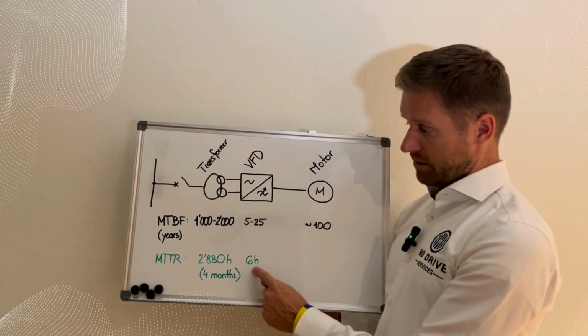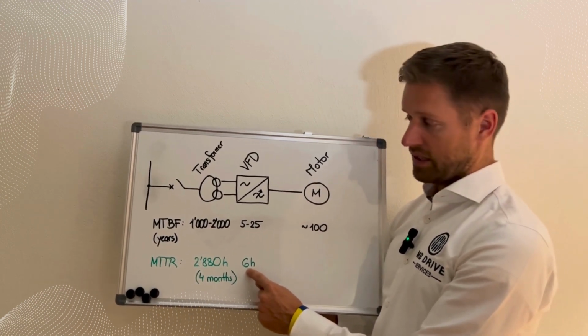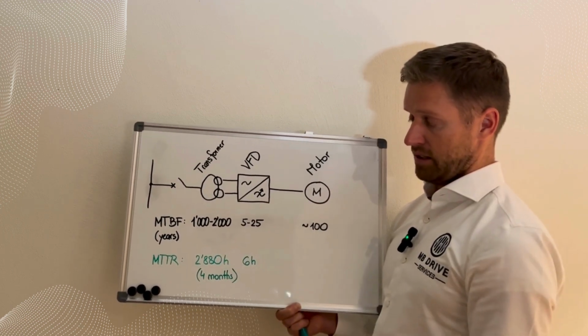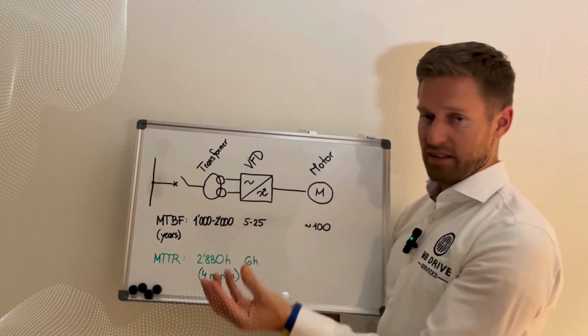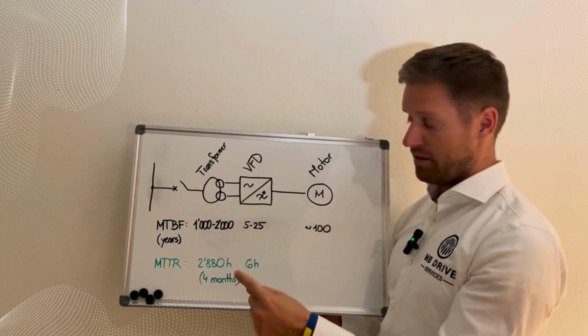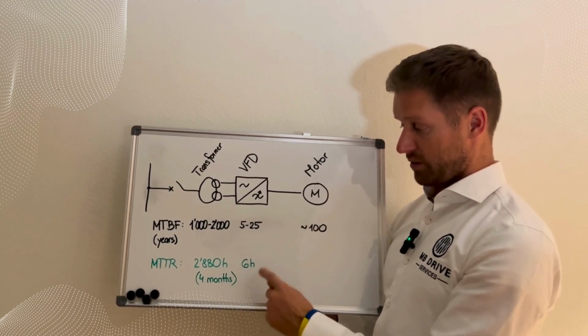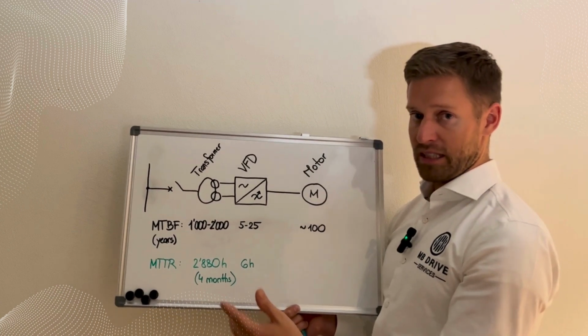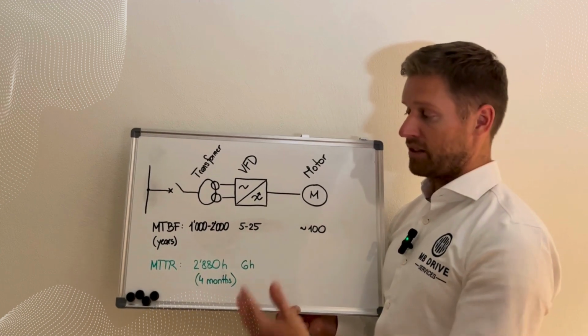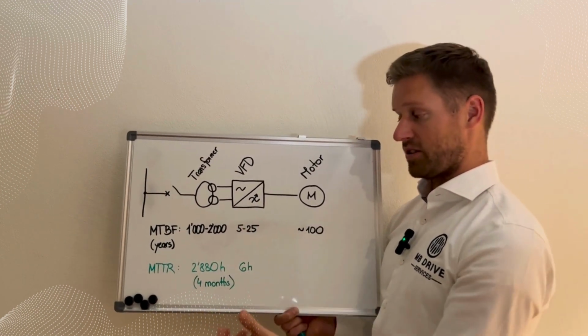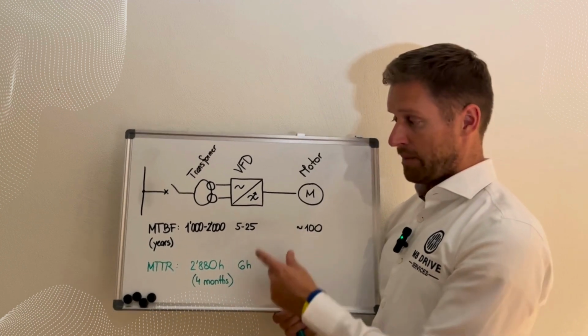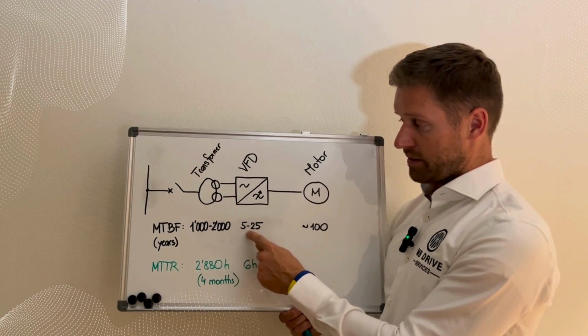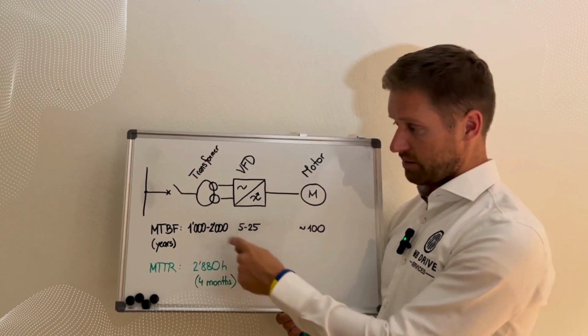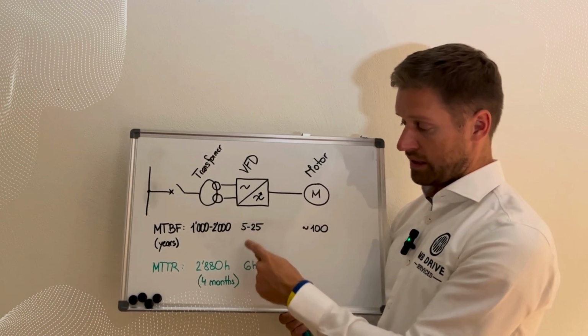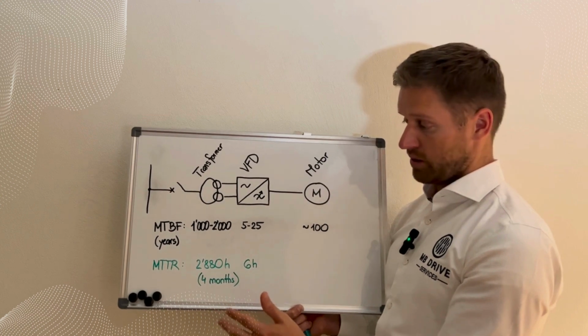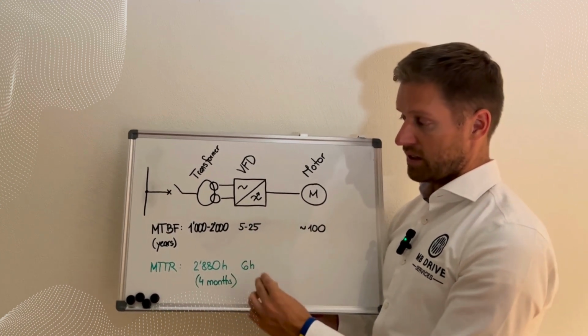But with respect to the MTTR, it's only a few hours. It can be that the semiconductor failed, and with most of the VFDs they are able to detect which semiconductor failed, and then if you have the spare part available on site, it could be even less than 6 hours. If the service personnel is trained for that operation to exchange the semiconductor, he can do it very fast. So the probability that you experience a failure in the VFD is much higher because the MTBF is shorter, but the rectification is also much shorter, so the impact of the failure is relatively small.